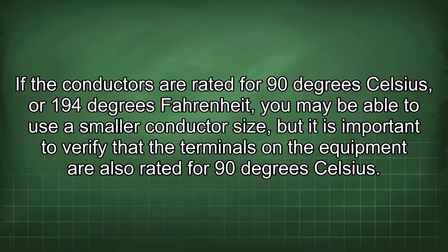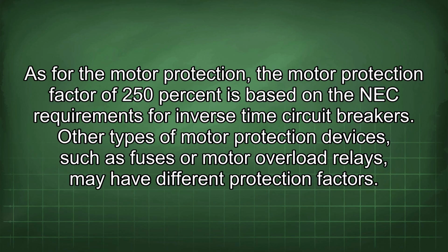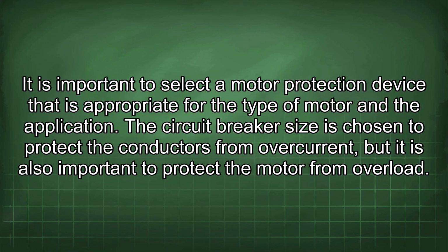degrees Celsius. As for the motor protection factor, 250% is based on the NEC requirements for inverse time circuit breakers. Other types of motor protection devices, such as fuses or motor overload relays, may have different protection factors. It is important to select a motor protection device that is appropriate for the type of motor and the application.